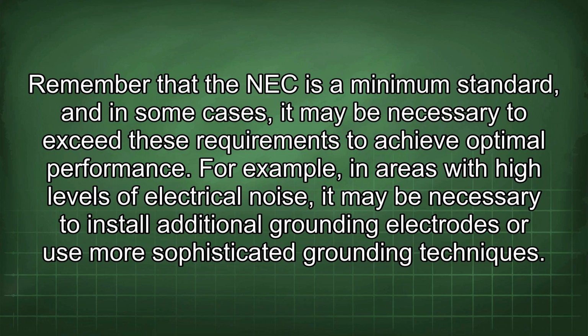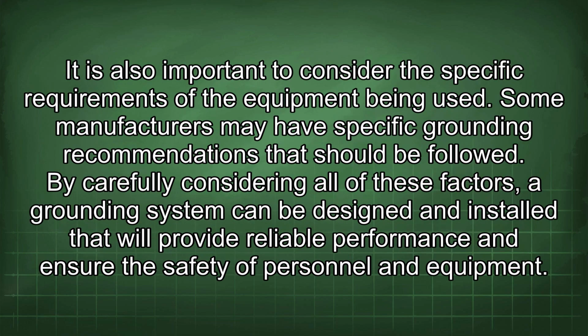Remember that the NEC is a minimum standard, and in some cases, it may be necessary to exceed these requirements to achieve optimal performance. For example, in areas with high levels of electrical noise, it may be necessary to install additional grounding electrodes or use more sophisticated grounding techniques. It is also important to consider the specific requirements of the equipment being used. Some manufacturers may have specific grounding recommendations that should be followed. By carefully considering all of these factors, a grounding system can be designed and installed that will provide reliable performance and ensure the safety of personnel and equipment.